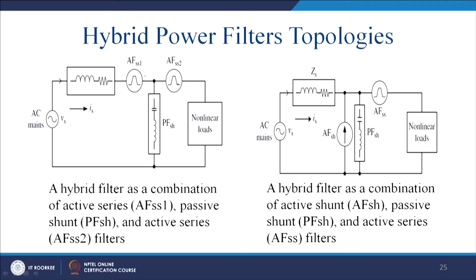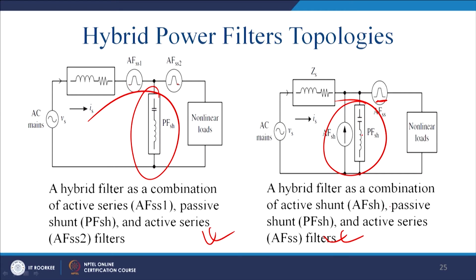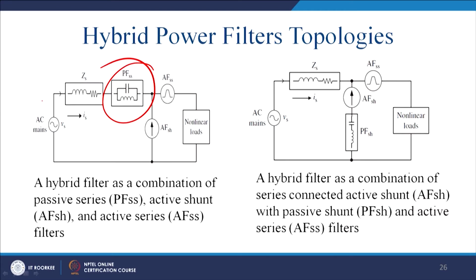Similarly, you can have two active series filters, and this can be a passive filter, and then you can have, sorry, pardon me, you can have two shunt filters. One is active, another is passive, and another is the series active filter. So, this is also a combination. Now, you have series passive, you have series active and passive. This combination is also a very useful combination. This one first mitigates the voltage harmonic arising mainly from the fifth and seventh, and ultimately this one will compensate the rest of the harmonic, thus the overall rating gets reduced, and the shunt part will compensate the current part of it.